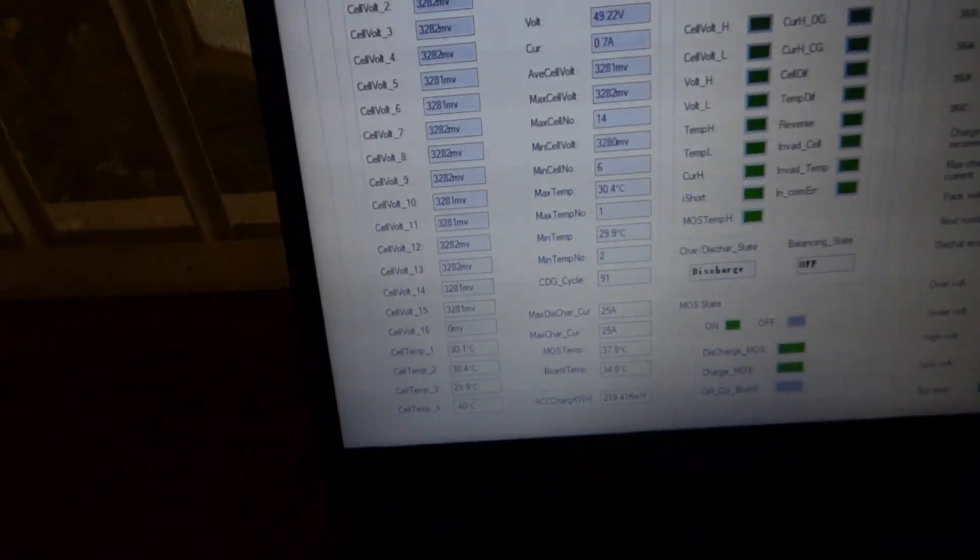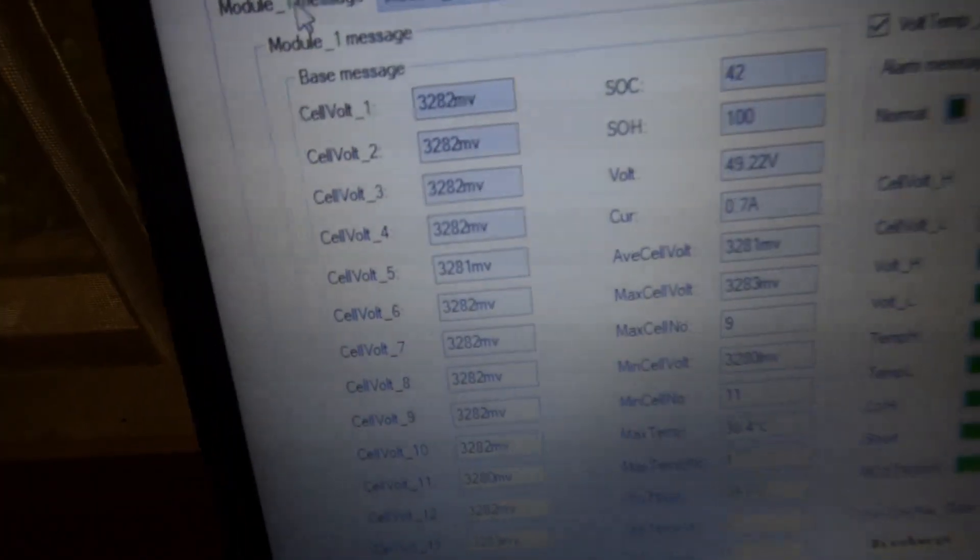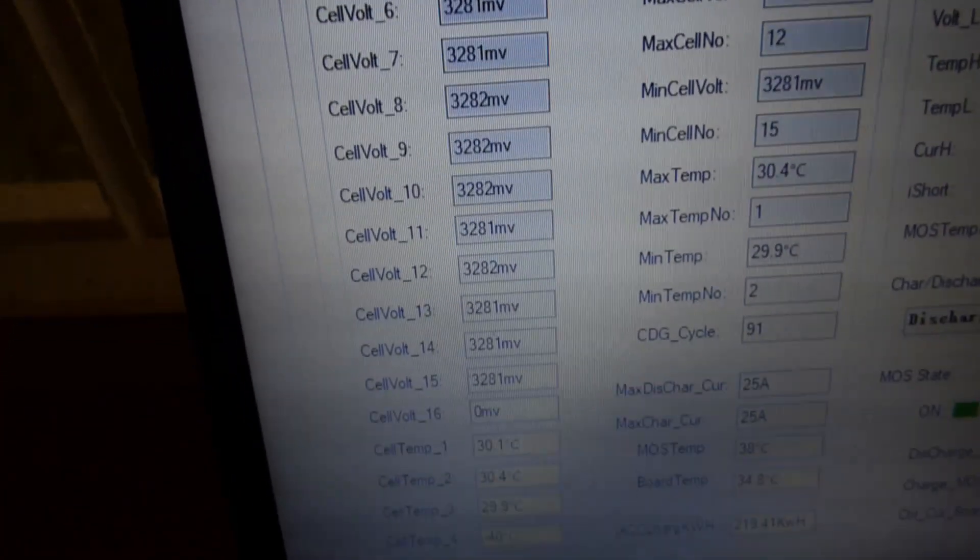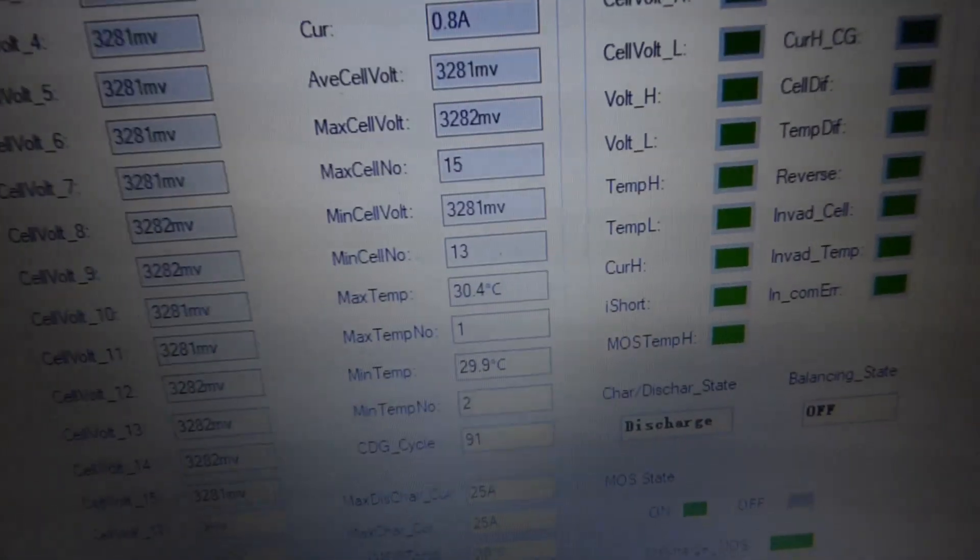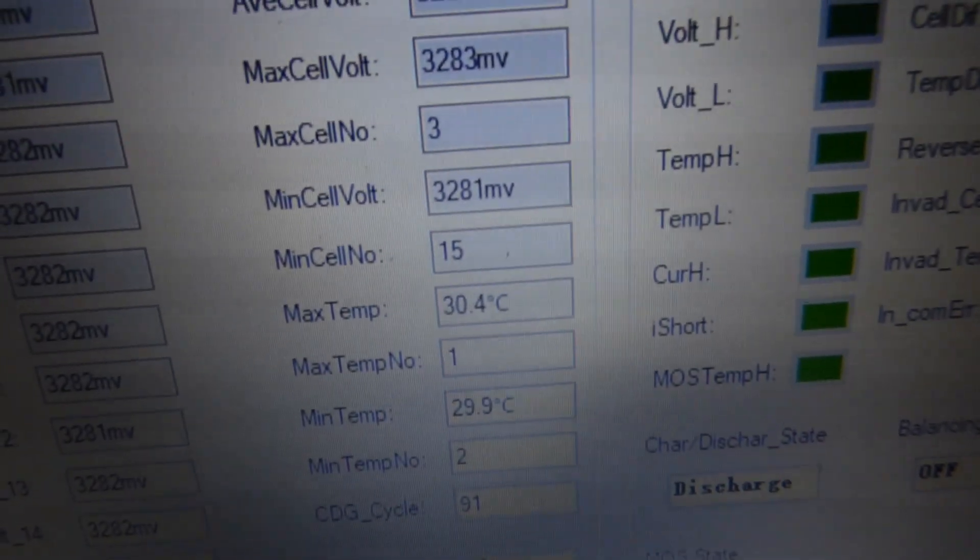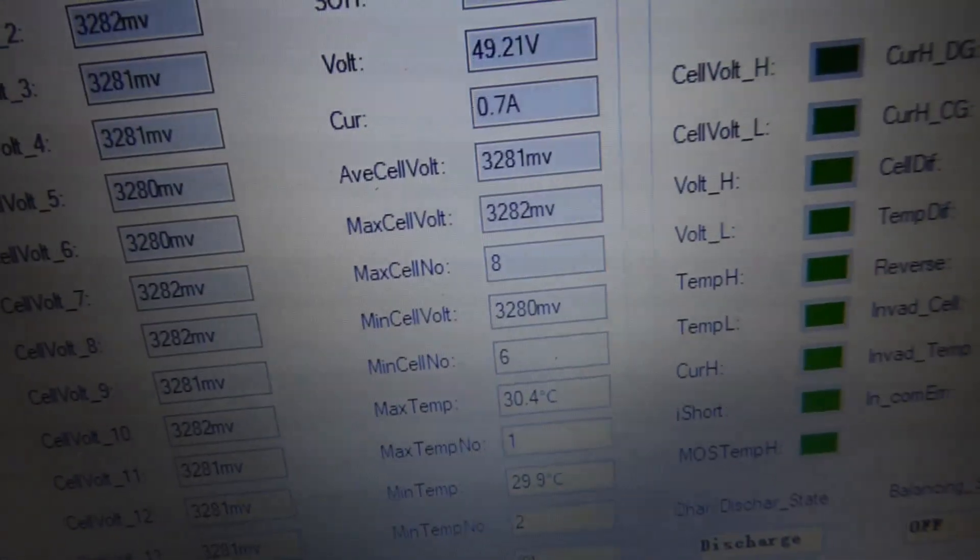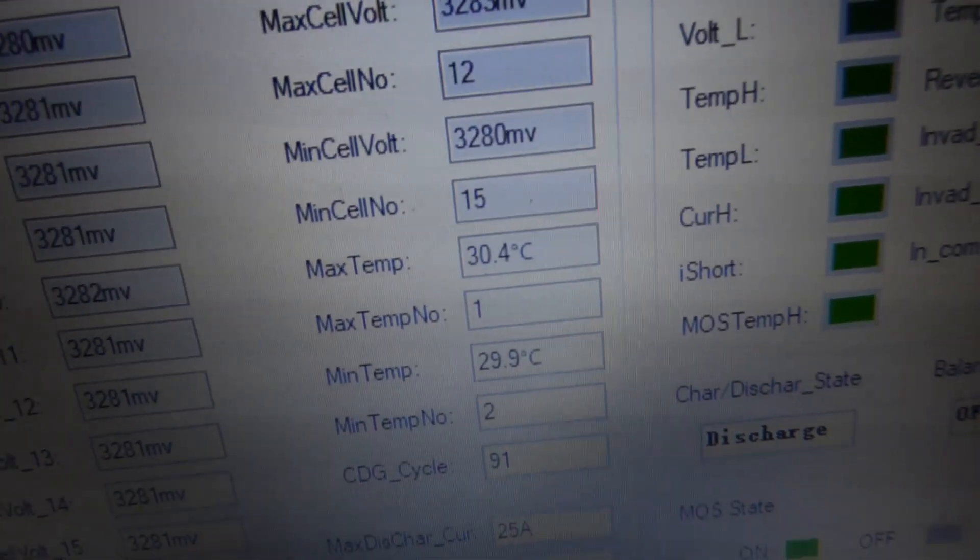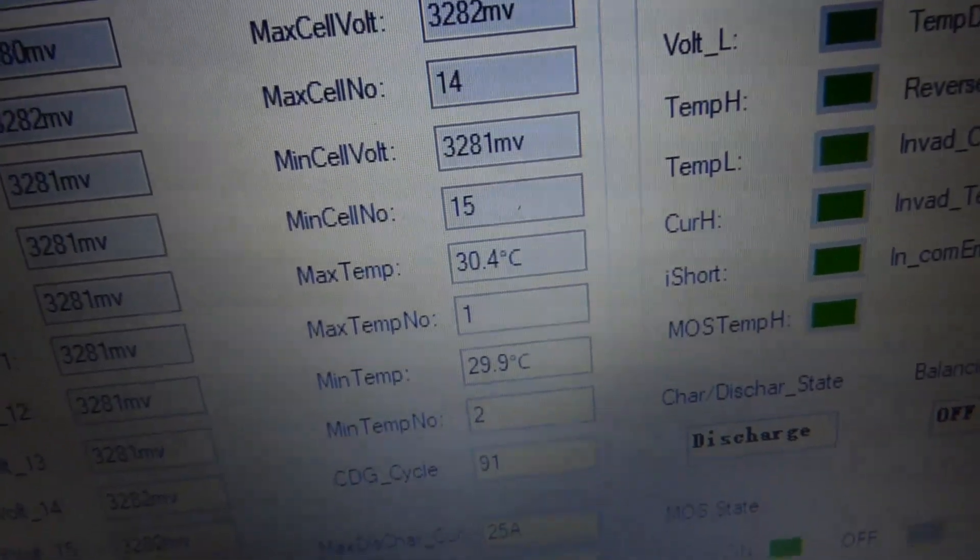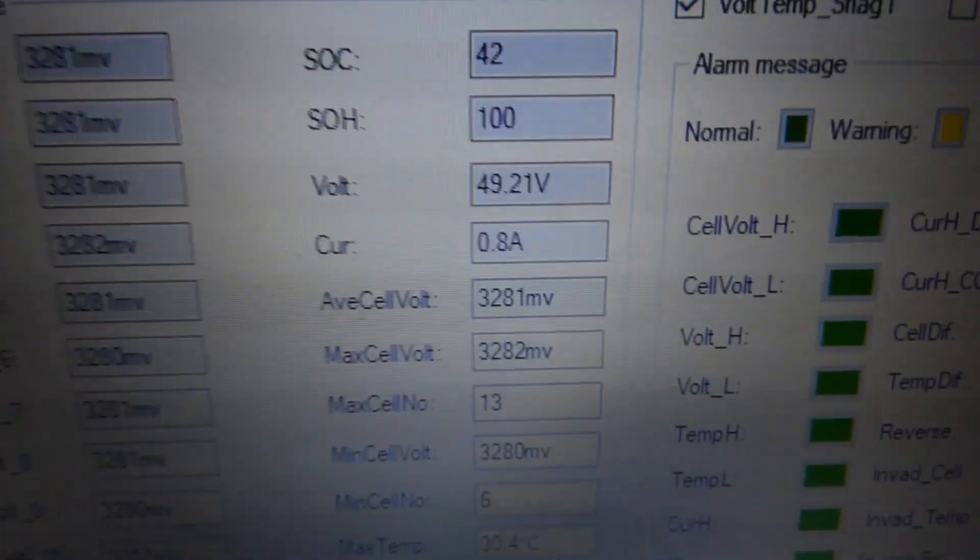So here is module number one. You could see the voltage of the individual cells. And then you could see the current that's being taken out. I think, yes, the batteries are discharging. So 0.7 amps. And then the difference, the max cell voltage, 3282 millivolts. And then 3280 is the minimum. So this is at 42%.